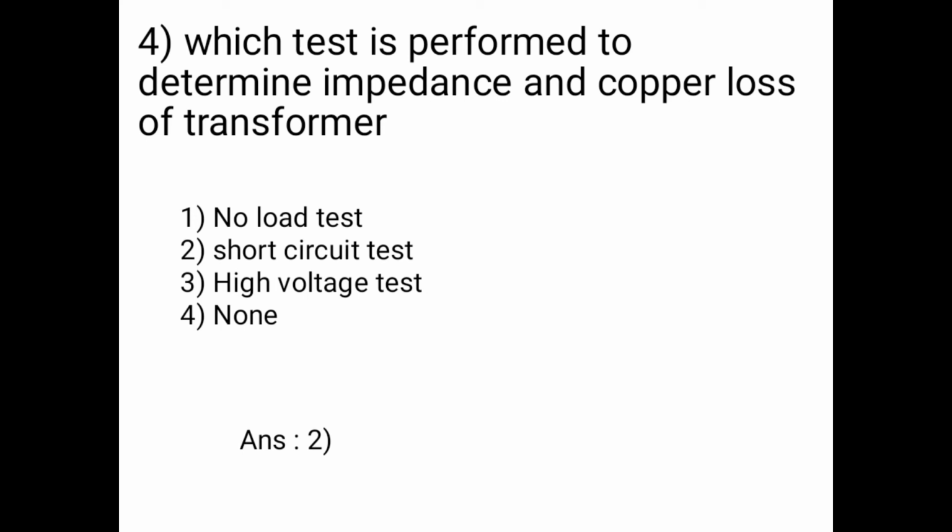Question number 4: which test is performed to determine impedance and copper loss of a transformer? Options are no load test, short circuit test, high voltage test, none. Answer is option 2, short circuit test. The short circuit test is performed to determine impedance and copper loss of a transformer.